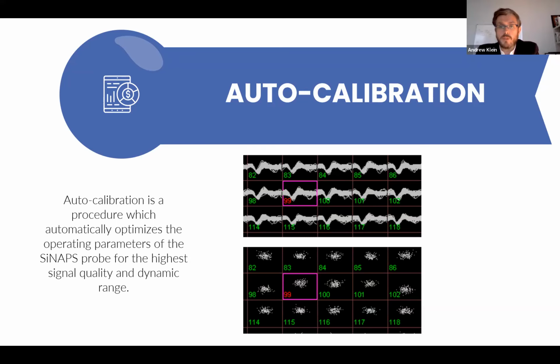First, after one or more probes are implanted, the probe tissue interface is left to stabilize for a period of 20 minutes. Next, this auto-calibration procedure is executed in OmniPlex to perform the final tuning of the probe's bias, after which stable signals can be acquired and recorded. After the auto-calibration has completed, any channels which were unable to be satisfactorily calibrated will have their channel numbers shown in red in the multi-channel views within Plex Control. This is shown in the screenshot from Plex Control on the slide. Typically, very few channels will fail to calibrate.